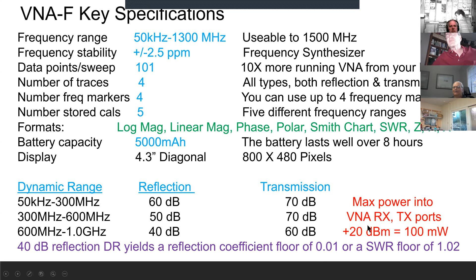So how does this really clever instrument work? First, I'll try to say it in words, and then we'll look at a picture. In the VNA, there's a stable dual frequency phase lock loop signal source, which can be stepped over frequency. It produces 2 signals that are spaced 5 kilohertz apart. One signal is E reference, and the other signal is a local oscillator signal. These signals are digital waveforms with fast edges, and therefore they have harmonics, making them useful up to approximately 1500 megahertz. The E reference signal is connected to port 1 of the device under test. The device under test reflects a signal E reflect back to a high-performance Wheatstone bridge, which separates the E reference and E reflect signals.